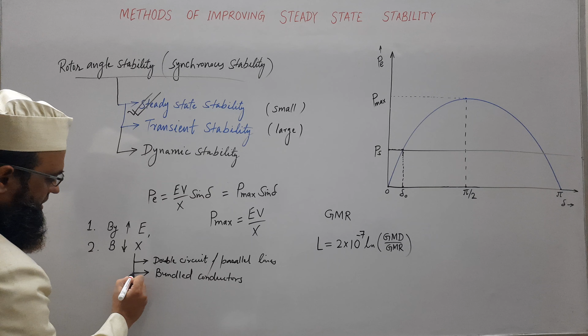We may further reduce X by using series compensation. So we are not going into detail on what series compensation is, just to understand: we have the inductance of the line, the uncompensated line, X. If you add a capacitor in series anywhere, whether sending end side or receiving end side or in between, corresponding to that series capacitor we will have some capacitive reactance Xc. So the net reactance may be written as X minus Xc.